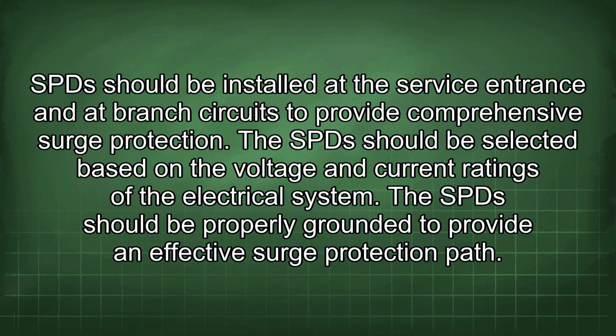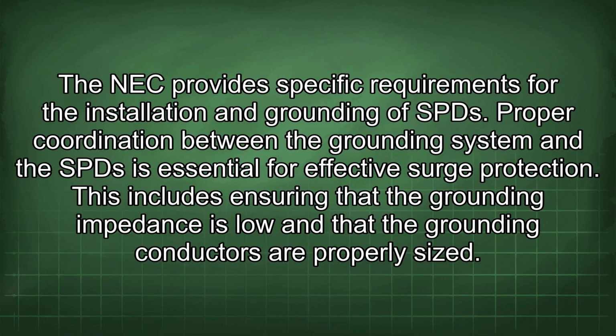SPDs should be installed at the service entrance and at branch circuits to provide comprehensive surge protection. The SPD should be selected based on the voltage and current ratings of the electrical system. The SPD should be properly grounded to provide an effective surge protection path. The NEC provides specific requirements for the installation and grounding of SPDs.